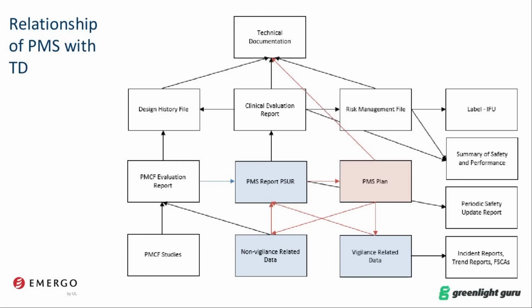And then this last slide, which is actually extracted from our procedure on post-market surveillance, emphasizes the importance of post-market surveillance with all the other regulatory documents and regulatory systems and processes. So we have here the post-market surveillance plan, which is described in Annex III of the MDR, and data from your post-market surveillance is included within all your other regulatory documents. It would be considered in your clinical evaluation report, in risk management, and would also lead to your periodic safety update report as well as your PMS report. So really, this is intended to depict all the important aspects related to post-market surveillance and how fundamental a system it is within the context of your quality management system and your regulatory documents.